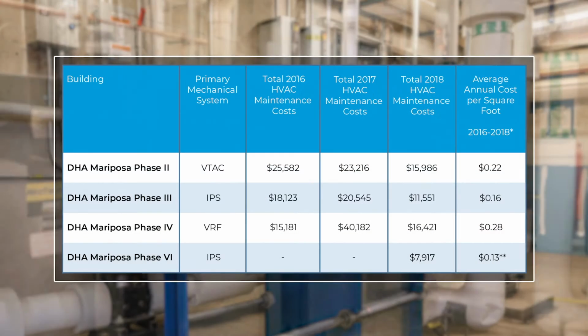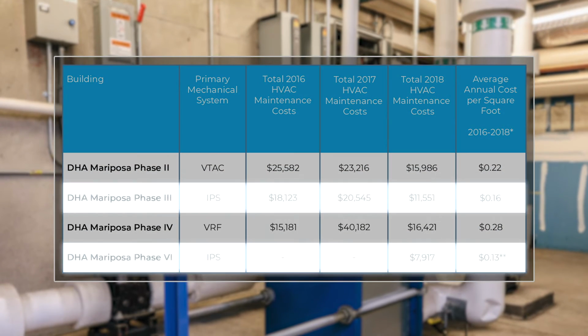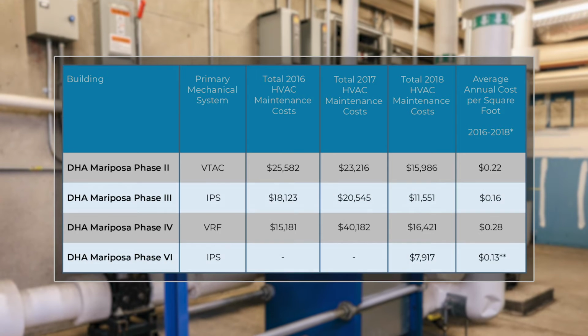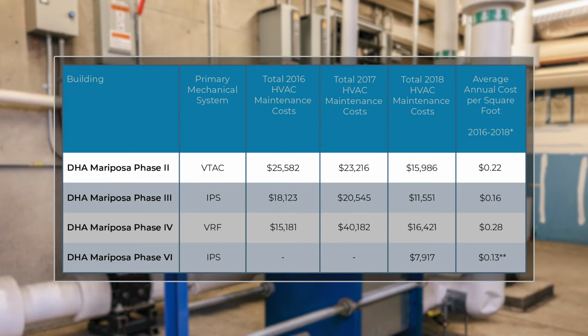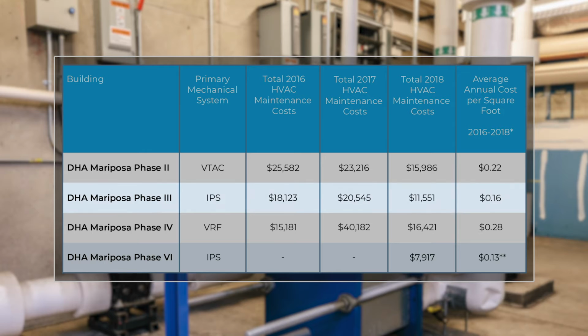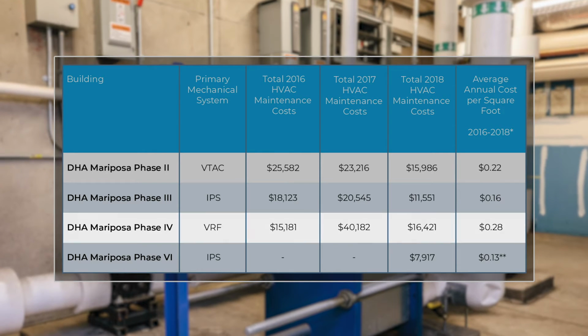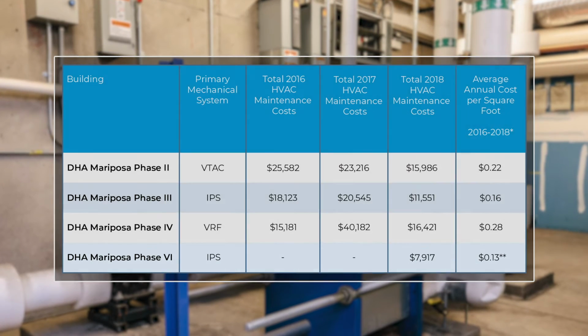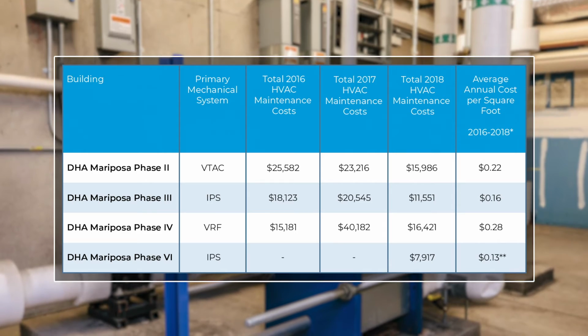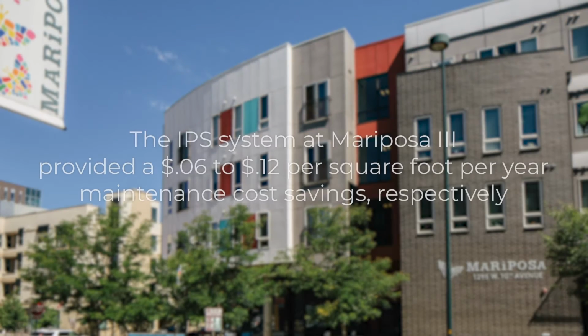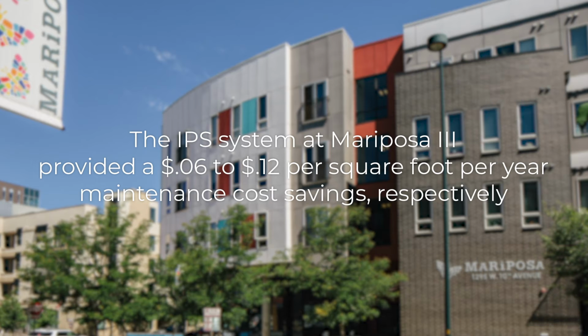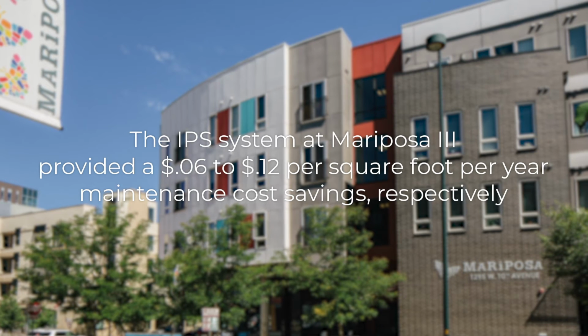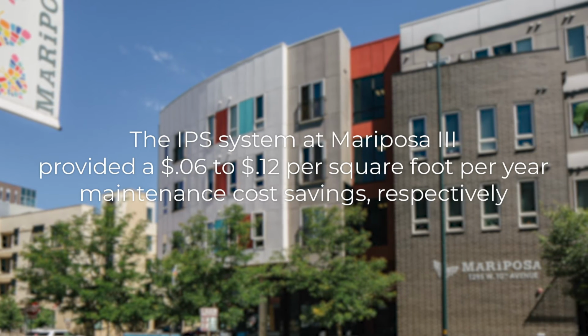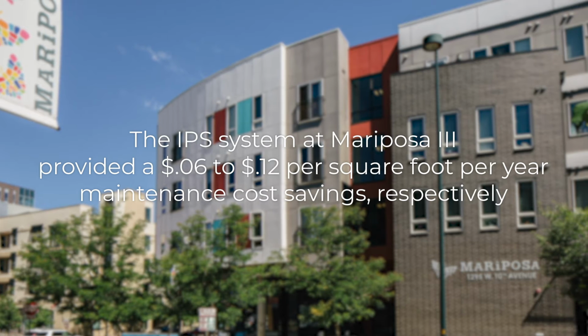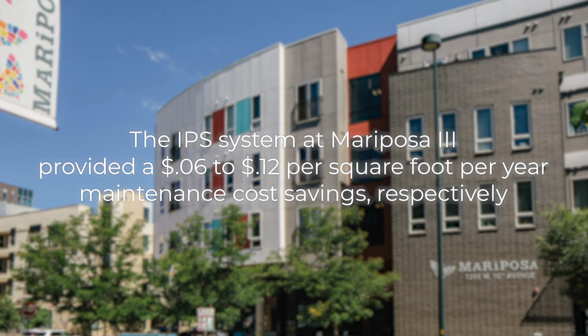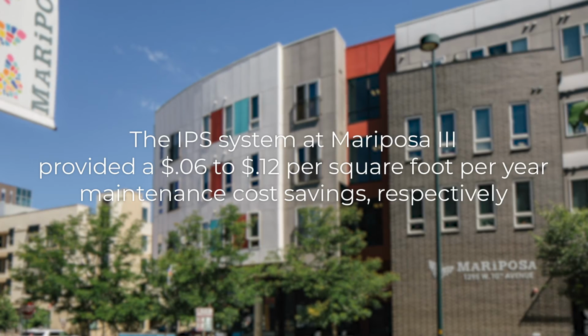And as far as maintenance costs go, IPS is the winner in this category too. Comparing nearly identical buildings held by the same property manager and served by similar maintenance contractors, we learned that compared to buildings with PTAC and VRF systems, the IPS system at Mariposa 3 provided a 6 cents to 12 cents per square foot per year maintenance cost savings, respectively. For a 100,000 square foot building, these savings add up.